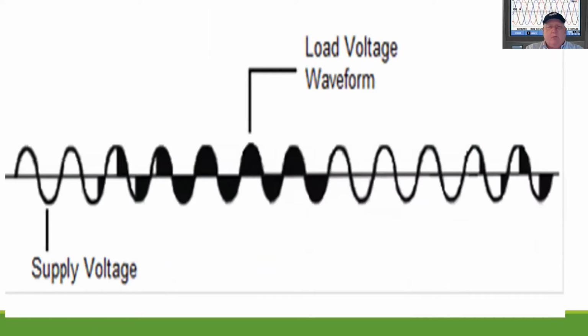So this is a waveform example of a soft starter. If you look at the power here that is coming along, this is the AC voltage. You can see here with the SCR, they start turning it on at a slower rate as the waves are going to it. So the motor doesn't see the average voltage, doesn't see it nearly as high. So the motor doesn't have that big spike. So you can gradually bring this up and let it operate. And then as you're in this running state, you're providing the full power. You're providing that full waveform, you're allowing it to operate.